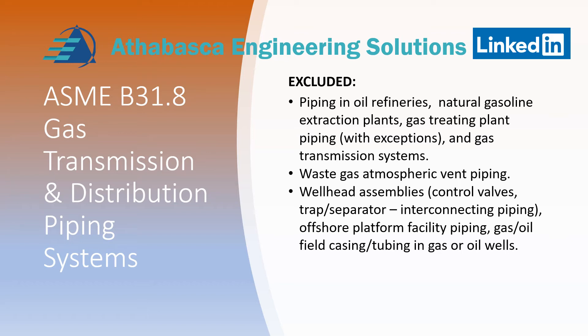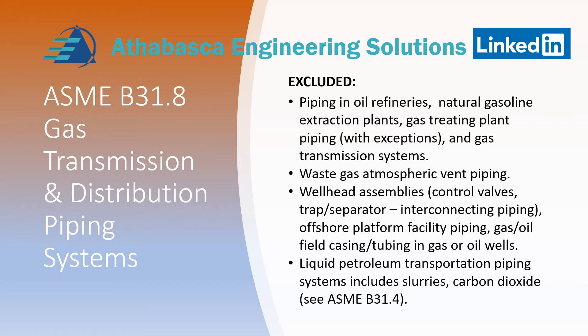Also excluded from B31.8 are control valves, trap separators, interconnecting piping, offshore facility piping, gas and oil field casing tubing, and oil wells. For any kind of liquid services, we go back to B31.4, and that includes slurries and carbon dioxide.